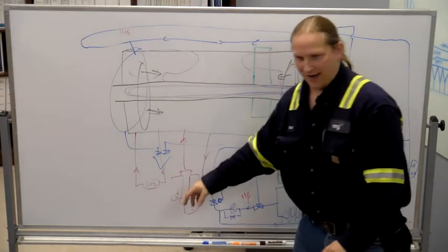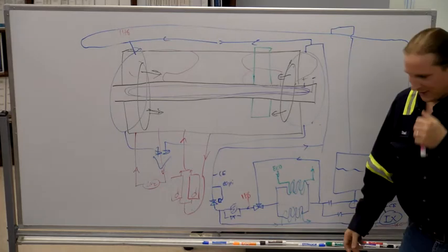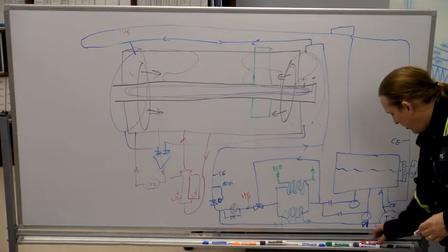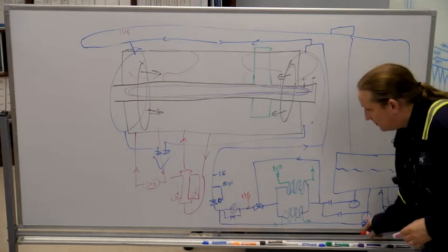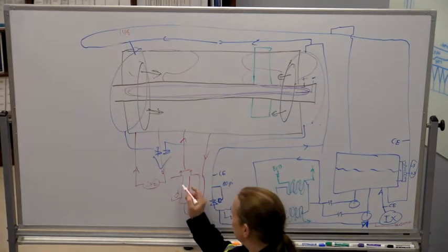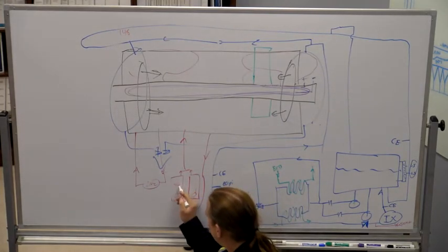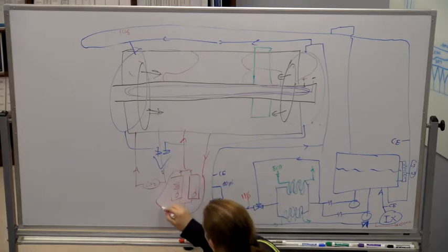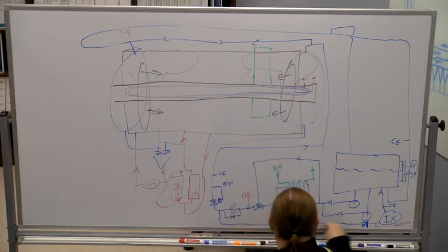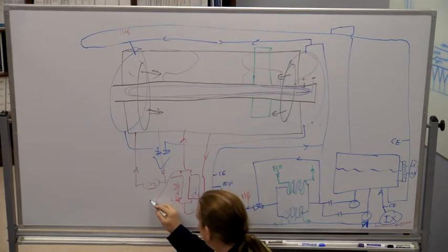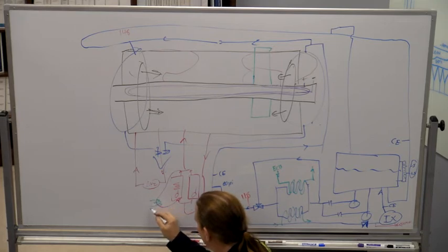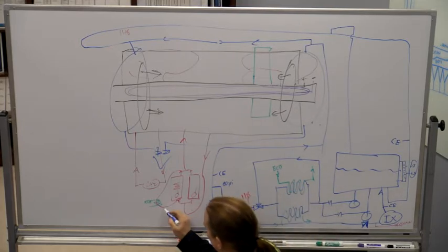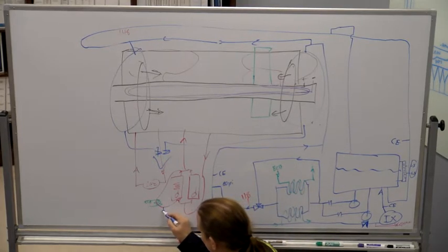I think it's on a timer. I just said that it looks at the dew point. I mean, we're measuring the dew point, but I think it's actually on a timer when it swaps. So then the tower that is not in service has to get rid of that moisture. So it's got a heater, and it's got a recirculating loop, and then it's got cooling water.